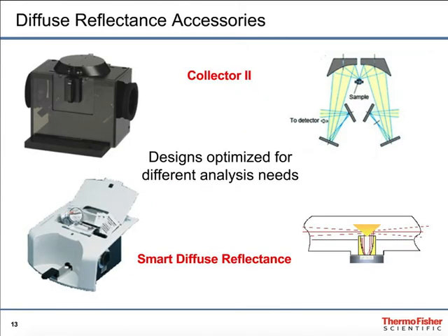Here are two of the accessories used in diffuse reflectance. At the top is the Collector 2 — you can see the sample located at the center beneath the clamshell of two mirrors on either side. This one is used very successfully in gemstone research, where diamonds or other gemstones are placed on that sampling location and the beam passes through them. The bottom one is a more classical diffuse reflectance setup, where the beam comes in, reflects off the sample, and is collected in a backscatter mode before being sent on to the optics.